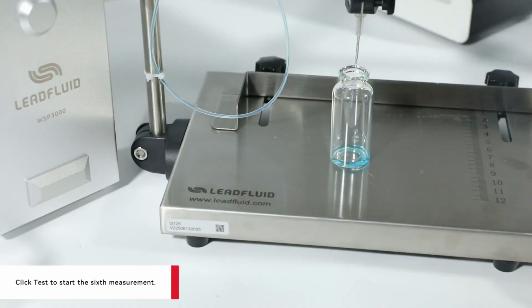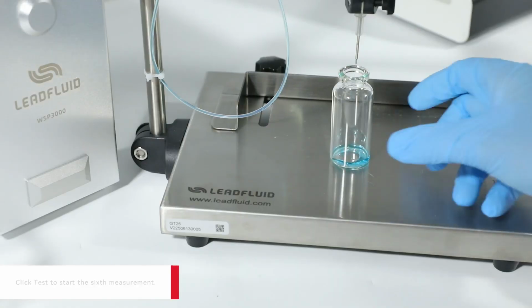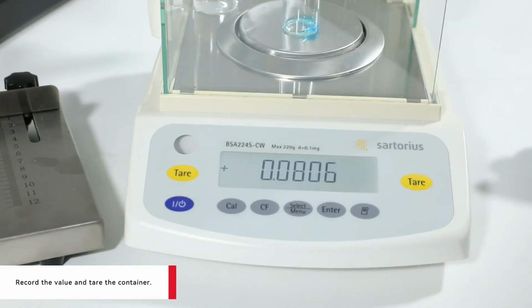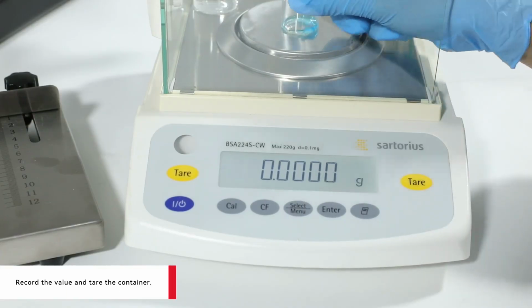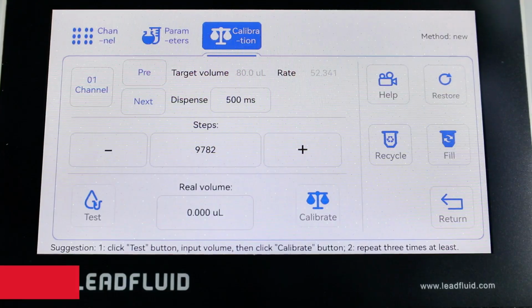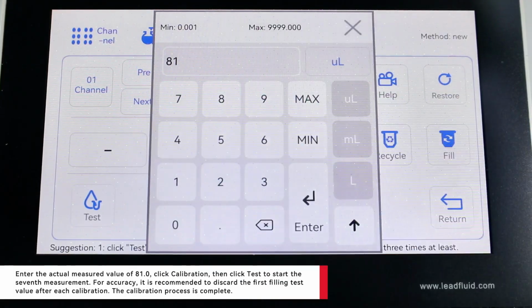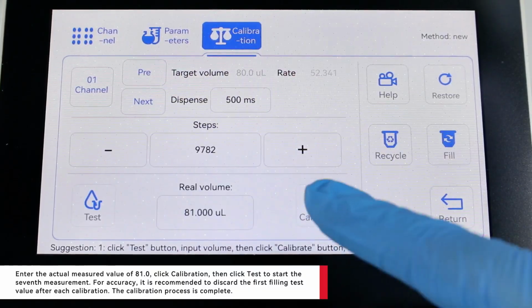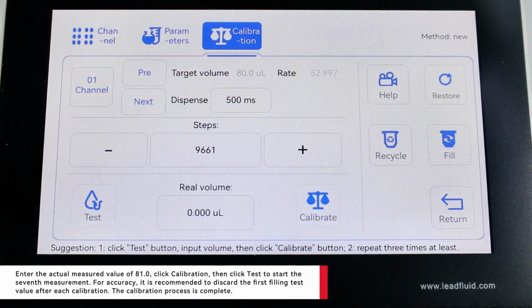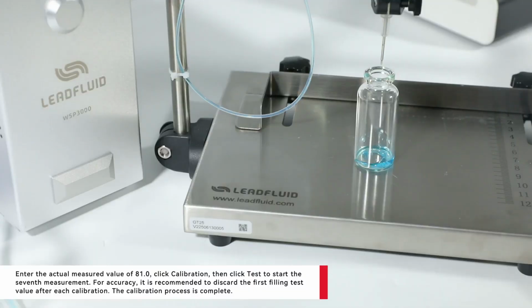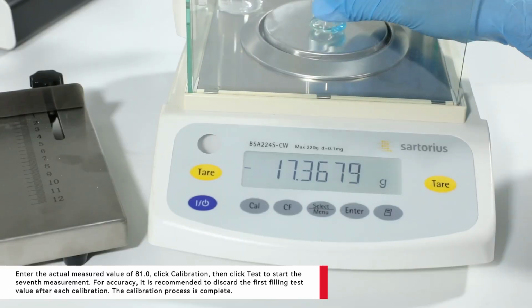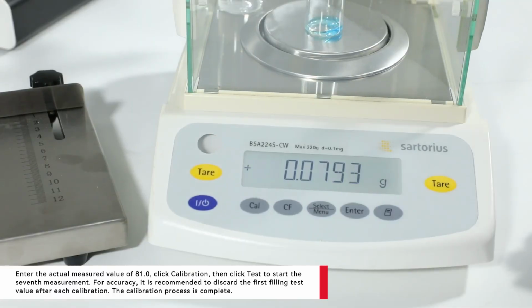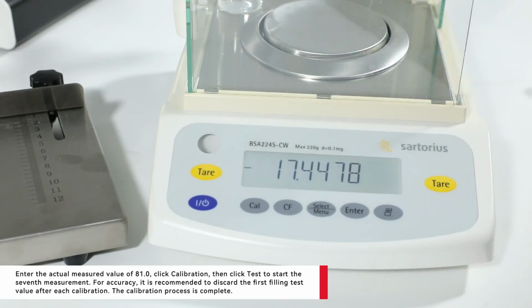Click Test to start the sixth measurement. Record the value and tare the container. Enter the actual measured value of 81.0. Click Calibration, then click Test to start the seventh measurement. For accuracy, it is recommended to discard the first filling test value after each calibration. The calibration process is complete.